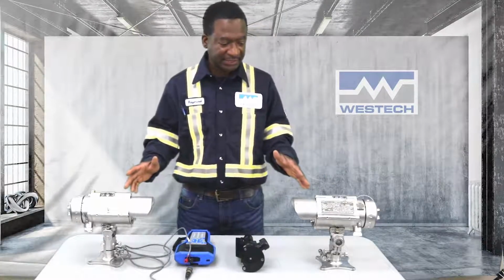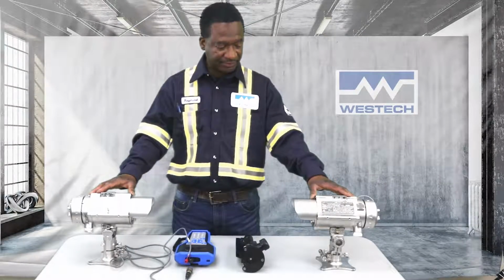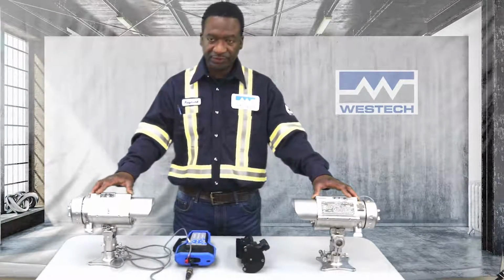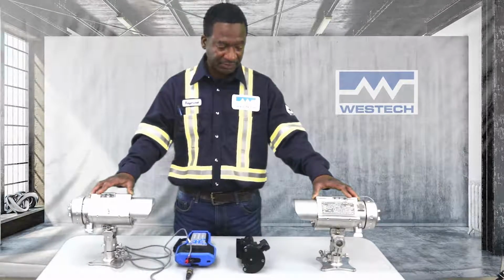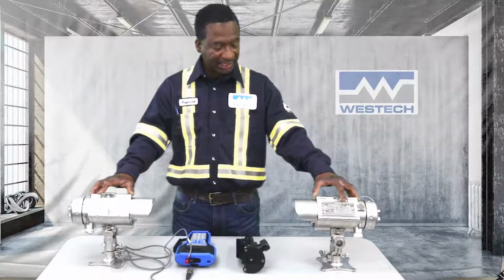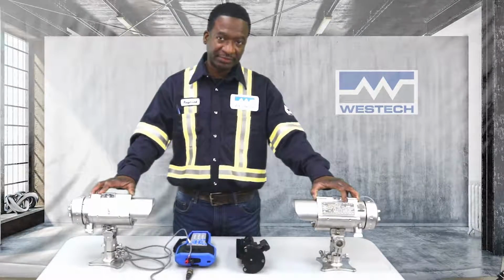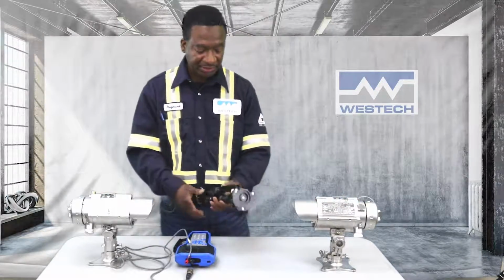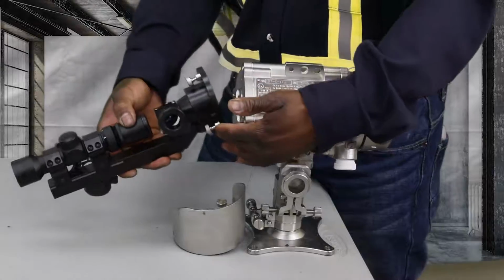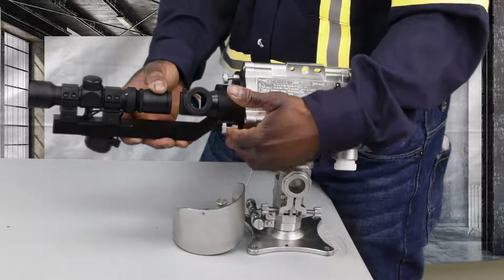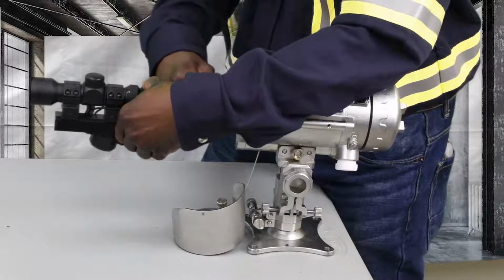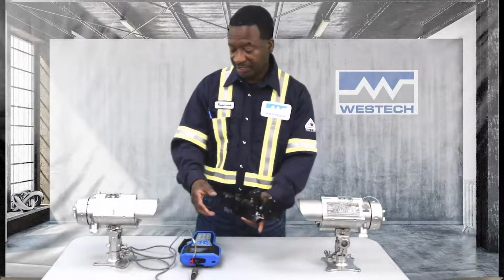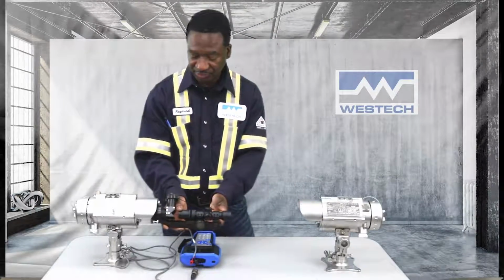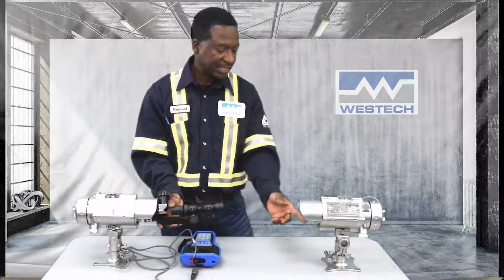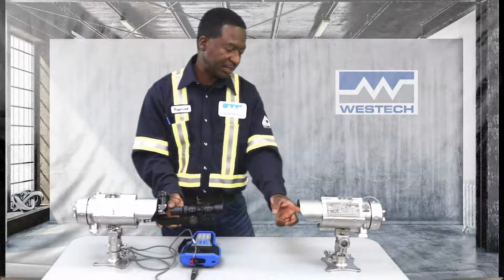It is important to note that 90% of the work done during installation is concerned with alignment of the detector itself. Open path detection systems need a clear line of sight without any obstructions, and it has to be aligned with a telescope so that the crosshairs are centered onto the center of the receiver in this case. And the same process is repeated whereby the telescope is bolted onto the face of the receiver and the crosshairs are in the center of the transmitter.